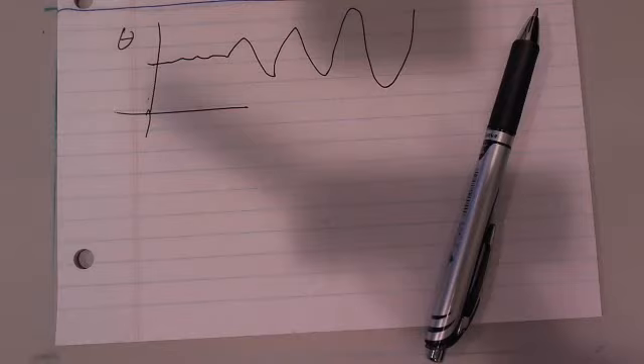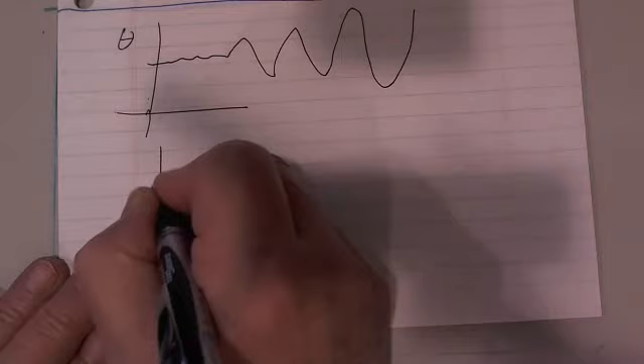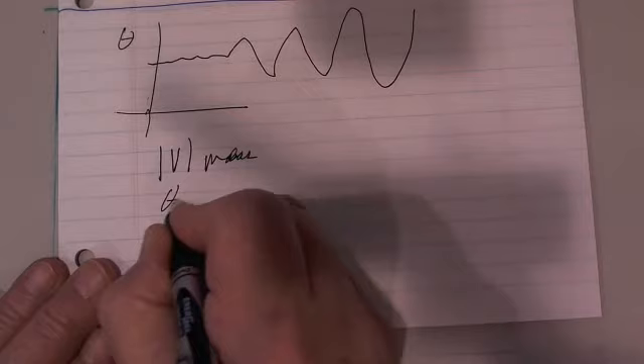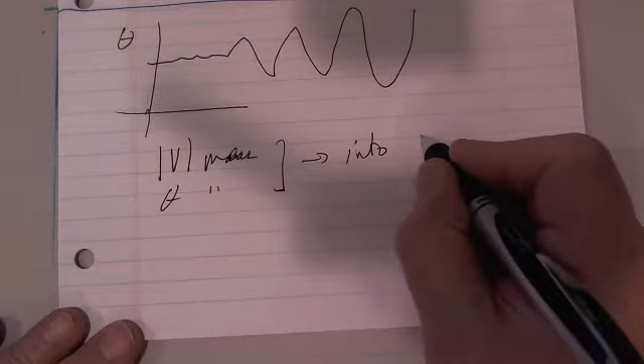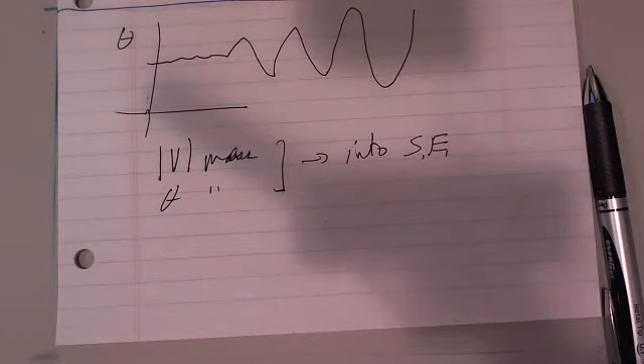But once again, we can put the magnitude measurement, and we can put theta measurement into the state estimator. It helps tremendously. The theta measurement helps tremendously with observability. That part has been brought out by a lot of people. Most electric companies have not said, okay, we're going to put a PMU unit that covers every single bus section in every major bus and every substation, et cetera, et cetera. They're putting them judiciously around their system because they're expensive. They are expensive to put in, but they do have that advantage.